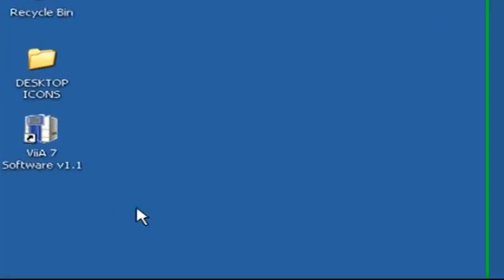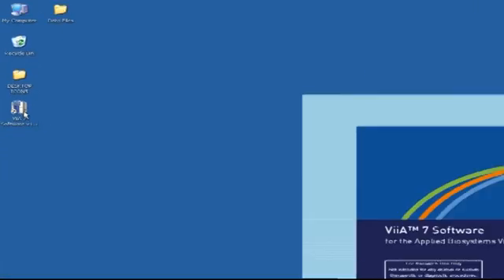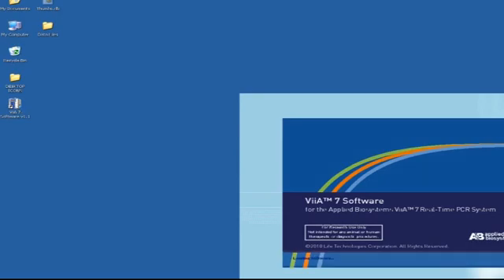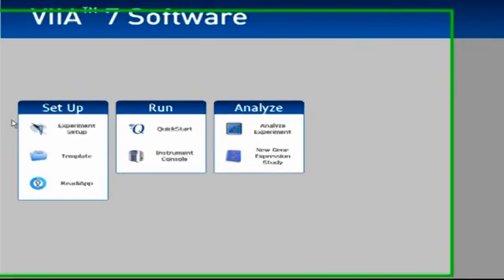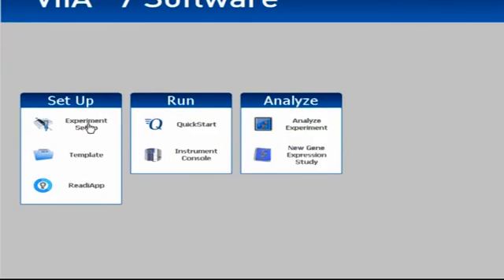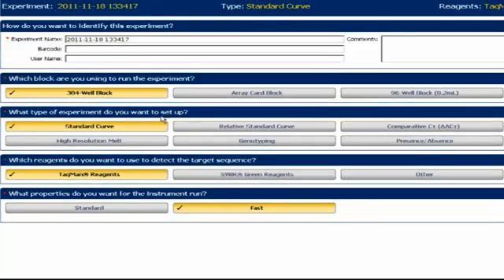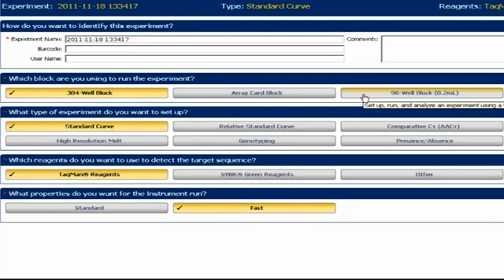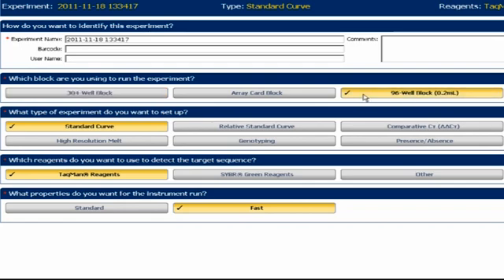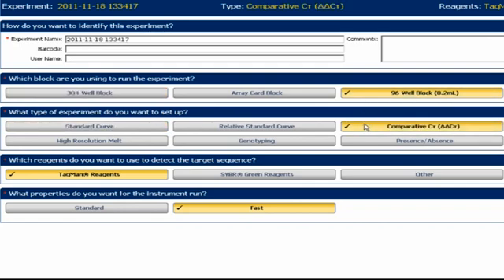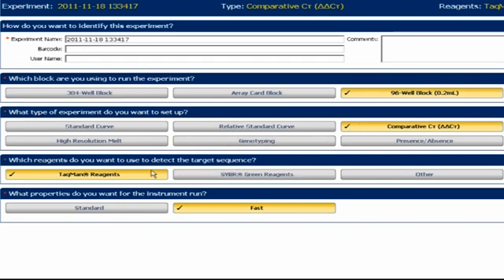Let's start by looking at the ViiA 7 version 1.1. From the home page, click on Experiment Setup. Next, answer a few simple questions. We'll pretend we're running a 96-well block. Next, we need to choose Comparative CT or Delta Delta CT as the experiment type.